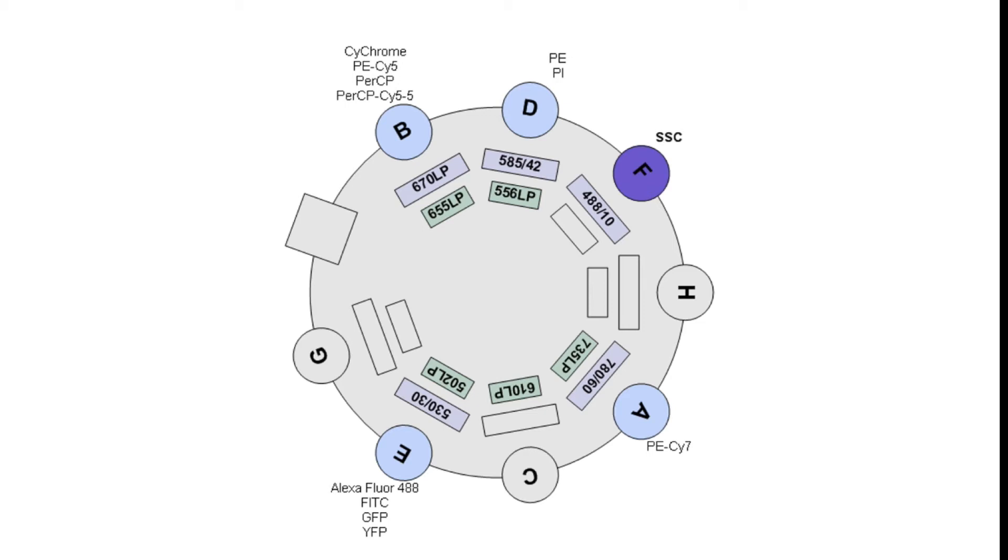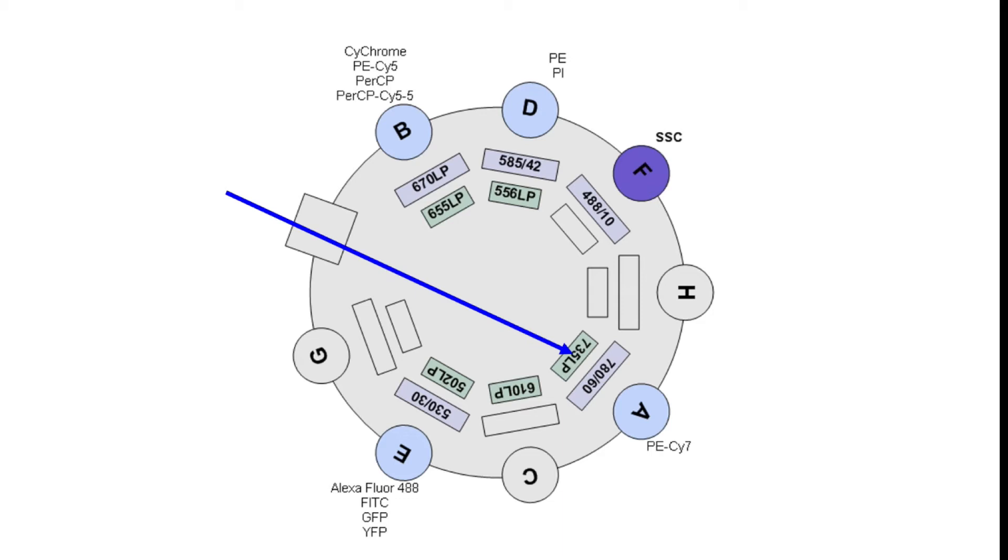In this instance the light passes into the filter set and first hits a 735 long pass filter. This means that any light 735 nanometers or longer will pass through this filter and be sent to a 780 slash 60 band pass filter. Now this band pass filter will then allow for a range of 750 to 810 nanometers, or a 60 nanometer band centered around 780 nanometers, and this light will be sent to the downstream detector.